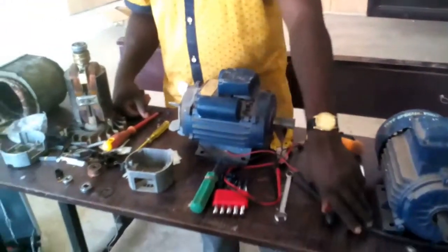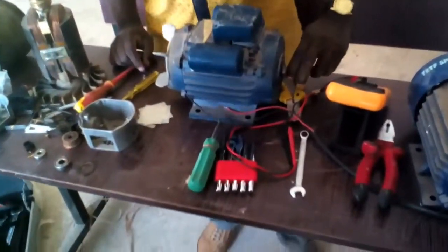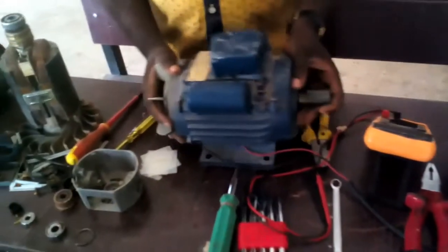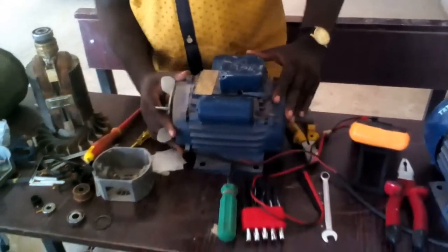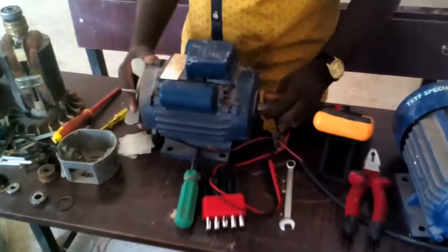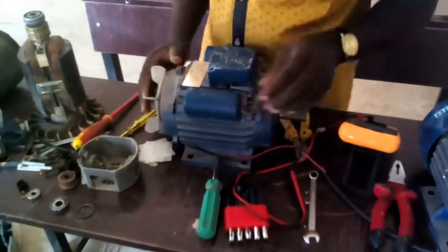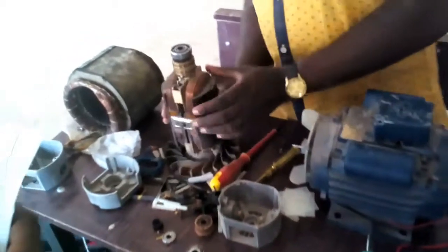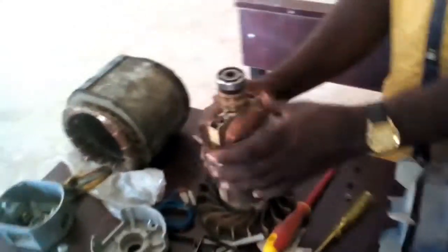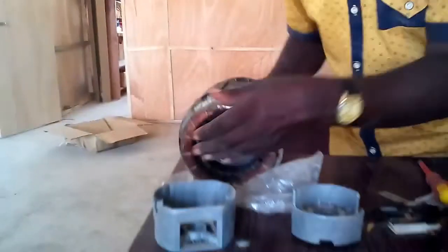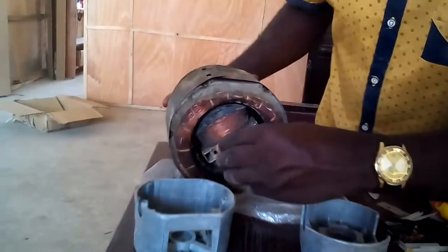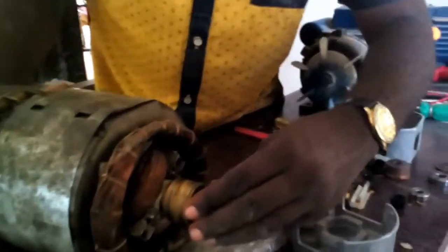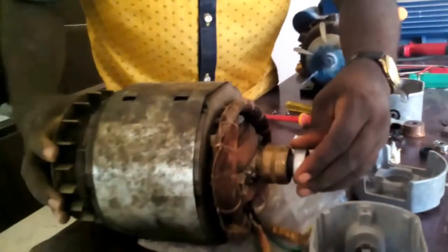We're going to look at faults in the machine again, and this time the problem is excessive vibration. If a machine appears to be vibrating excessively, what are the likely possible causes and remedies? By the time a machine is vibrating excessively, the likely cause will be from the rotor side. If the rotor is worn out or defective, there is a likely tendency that it will vibrate excessively. As you can see from the demonstration here, if the rotor is worn out or defective, then by the time it is rotating, the machine will be vibrating excessively.